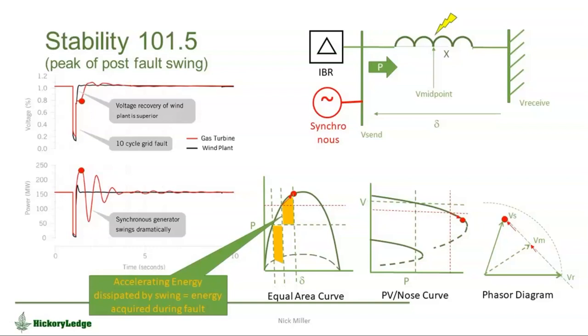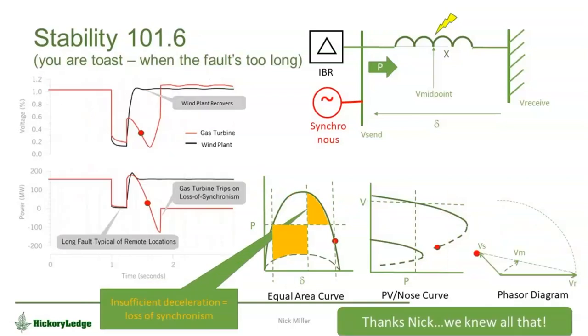So everybody should recognize this. You may not have been used to seeing the PV curve with the equal area curve and the phasor diagram all at once. But otherwise, this is stability 101. And just to remind you, I've been using this slide for this figure for 15 years, if the fault is too long, then the energy accumulated by the machine during that point when it can't get the power out, but the power is still coming into the drivetrain, is such that it can't be dissipated. So the orange rectangle-y thing is bigger than the orange triangle thing. We slide over the top of the PV curve, the phasor angle pulls apart, the midpoint voltage collapses, and you are toast.